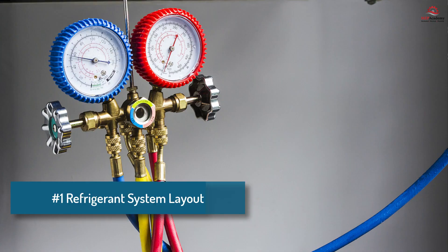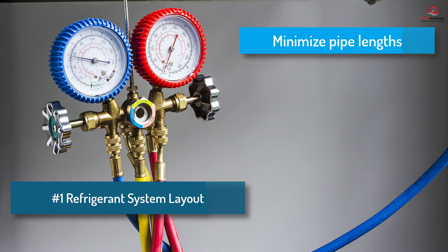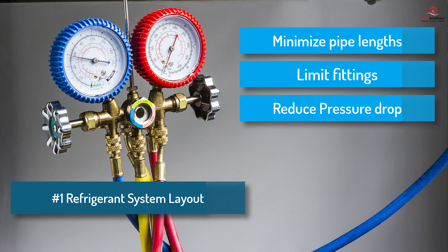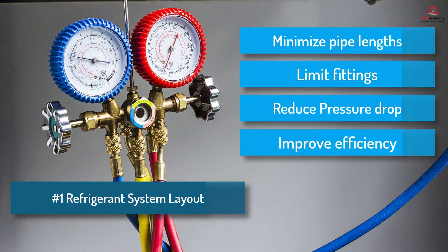1. Refrigerant system layout. The layout of the refrigerant system should be designed to minimize the length of the piping and the number of fittings and in-line components required. This reduces pressure drop in the system and helps improve efficiency. The total length of the refrigerant piping must not exceed the manufacturer's requirements, as this could result in a loss of capacity.